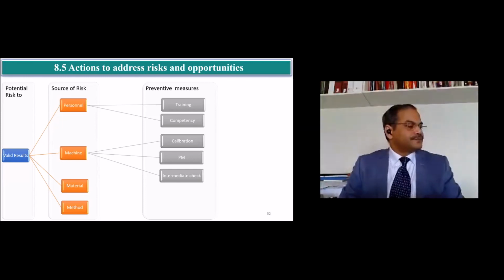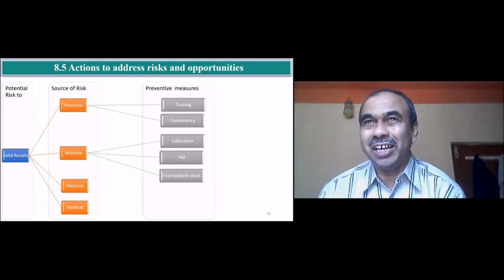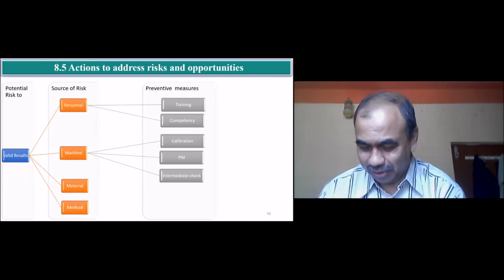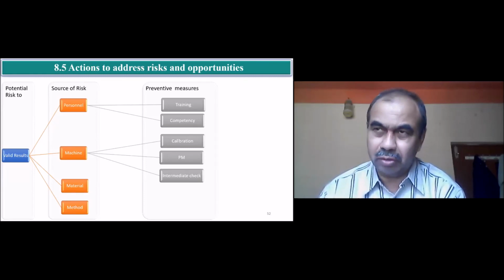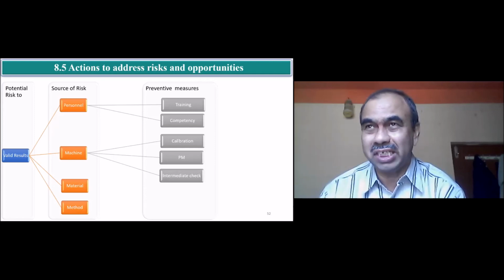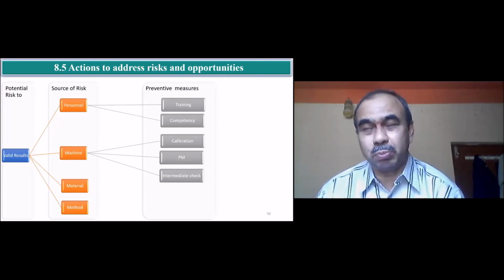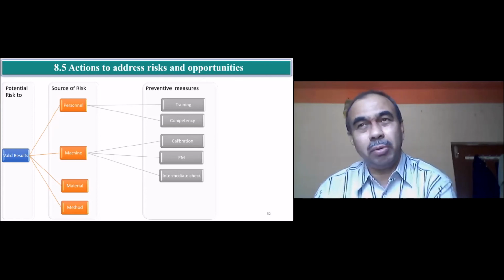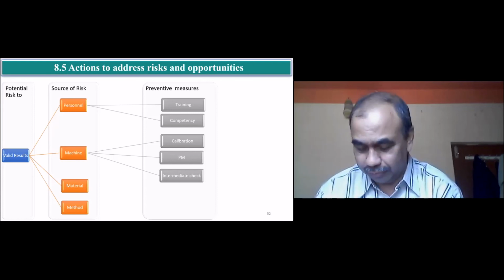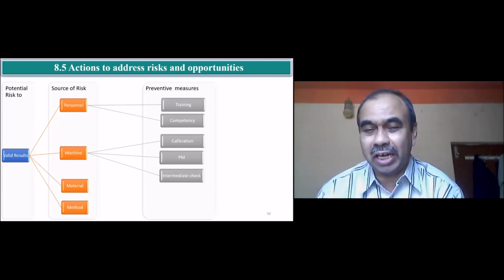I have taken up the calibration. Calibration is a process to ensure that you get validated results in your process. So how to handle the calibration? We have to first check, going through the PDCA cycle, whether you have sourced an approved supplier who is accredited to your requirements, especially 17025. That laboratory also should be accredited with 17025. So here the risk involved is the accreditation of the external source performing the calibration.